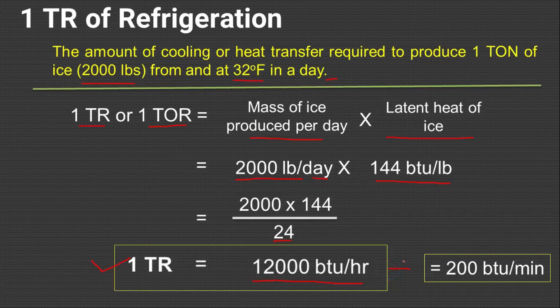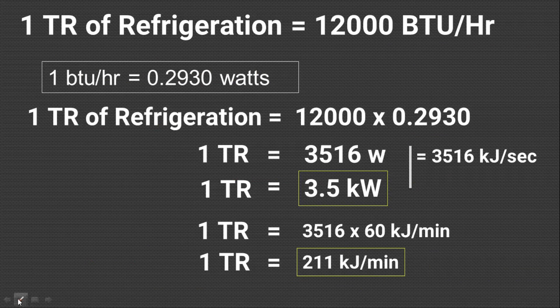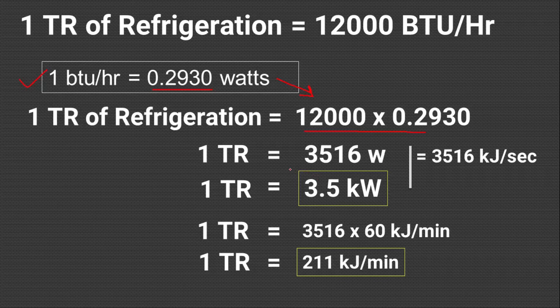To convert it into BTU per minute, we divide by 60 minutes, and it gives 200 BTU per minute, which is again a unit of 1TR itself. As we already know, 1 BTU per hour is equal to 0.2930 Watt. Hence we can convert 1TR into Watt or Kilowatt. So 1TR of refrigeration is 12,000 multiplied by the conversion factor 0.2930, which gives 1TR equal to 3,516 Watts. Hence, in short, 1TR is equal to 3.5 Kilowatts.